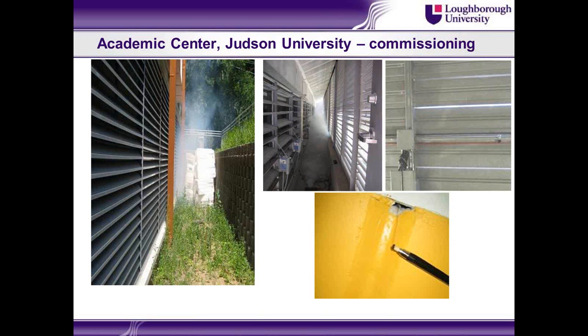Some remedial work was required there. I also highlighted the windward and leeward dampers in the earlier slide, and the control logic was the opposite way around there. They were opening the windward and closing the leeward, thinking that that would encourage more air into the space. And the partitioning in the attic space, partitioning according to the dampers, which dictated how much air got recirculated and how much air left. The control logic was wrong in that area there as well.